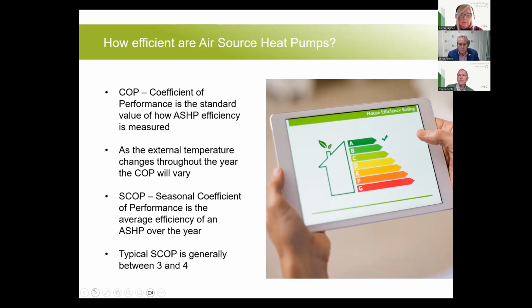Now, that's not really very helpful because obviously the outside temperature can vary an awful lot, and with some weather compensating controls, we can vary the inside temperature. So what the manufacturers have done is calculate how many hours in a typical year it is -5, -3, -2, -1, and so on. Overall, they've worked out all the efficiencies at those different temperatures and conditions to give you a SCOP. SCOP stands for seasonal coefficient of performance. So as engineers, and if you're trying to make a judgment to buy one of these things at home, that's the key ingredient you need to look for when selecting heat pumps, because the seasonal efficiency gives you an overall number, I'd say 3.9, 4.5, of what the machine efficiency is typically going to do over a heating season.